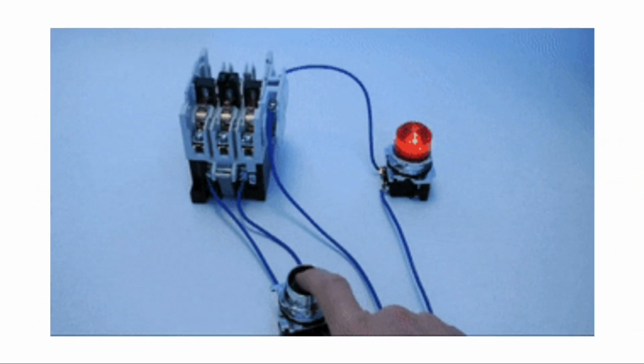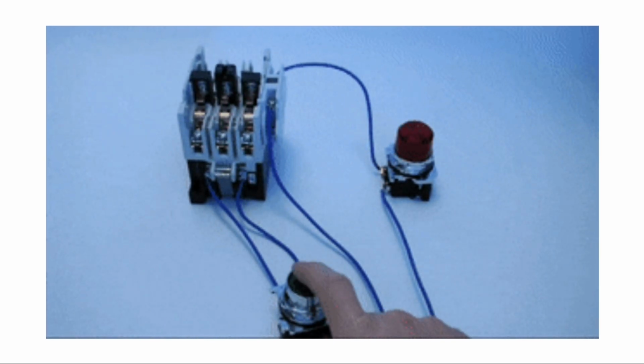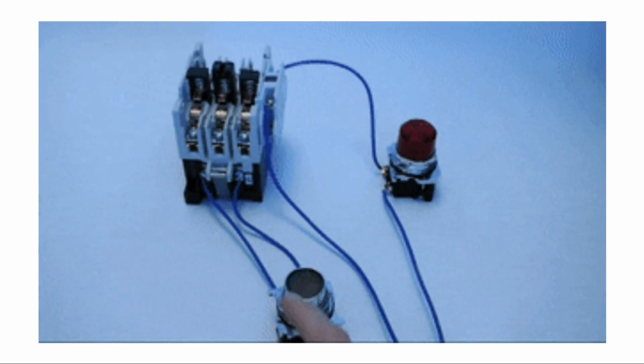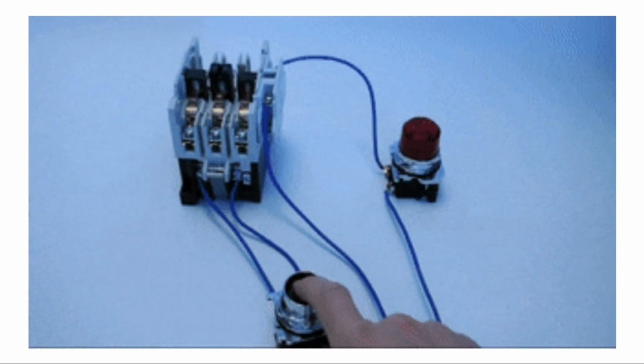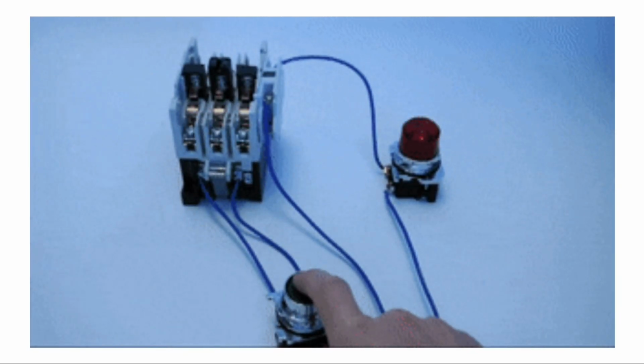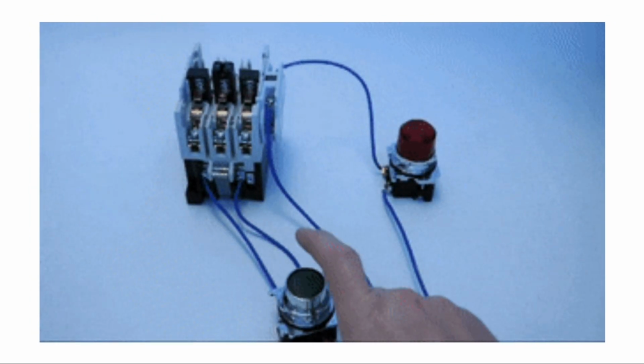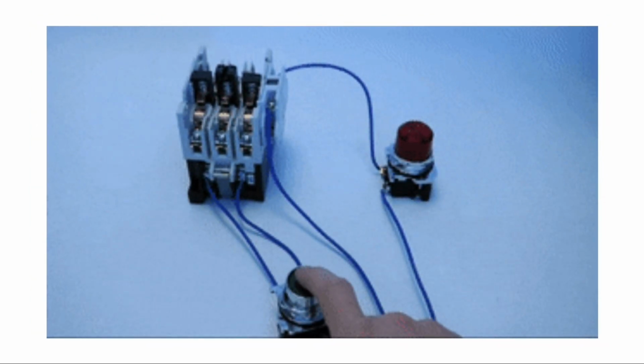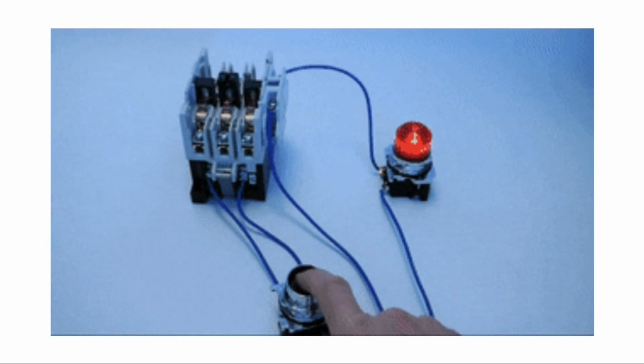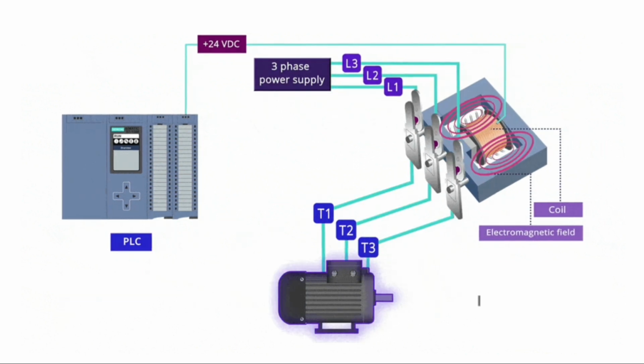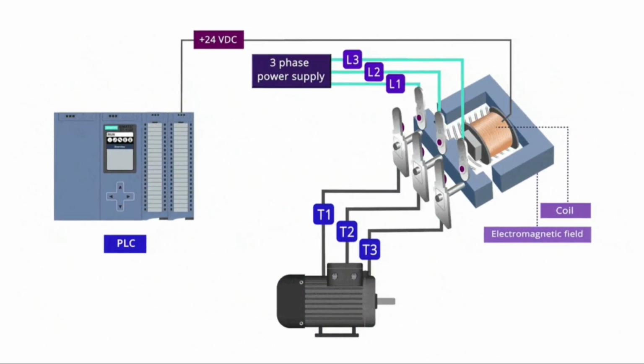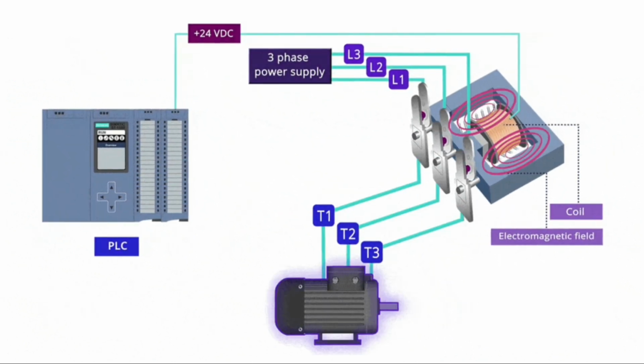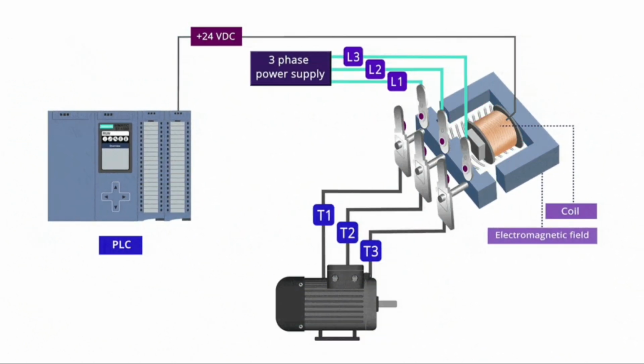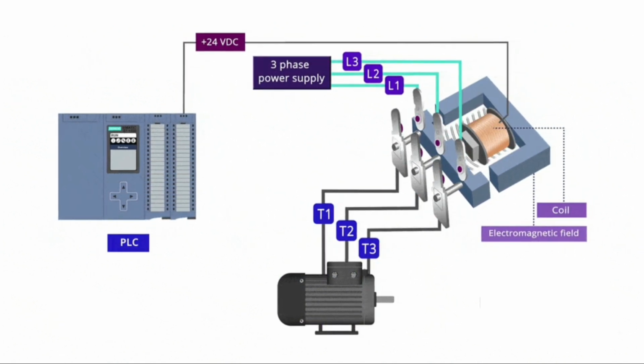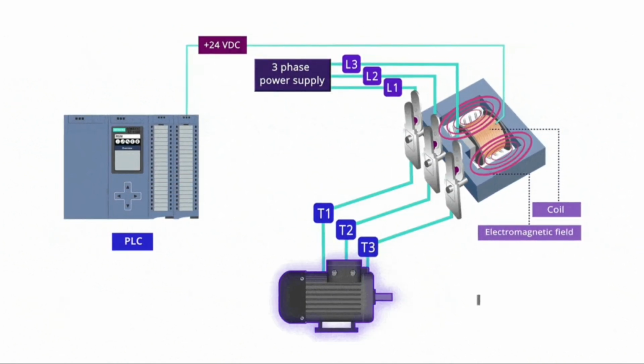So, there is no electrical connection between the coil and the contacts. The contacts will open and close via the electromagnetic field created by the coil. In the normal state, when the coil is not energized, the contacts are open, and when a 24-volt DC signal is sent from the PLC, the coil will be energized, the contacts will close and the motor turns on. With this setup, there is no direct connection between the PLC and the motor. That's how you can turn on and off a big high voltage electric motor indirectly and safely and make sure your PLC card won't be damaged if there are any electrical surges on the motor side. So that's why we use a contactor.